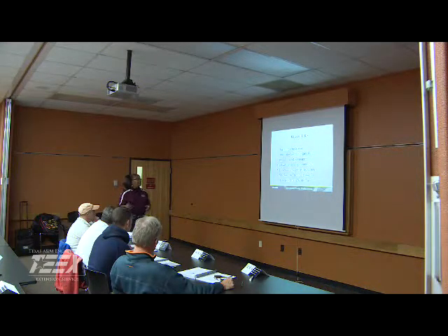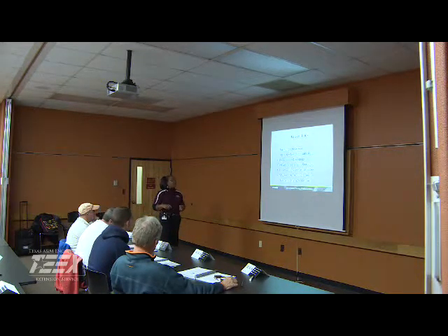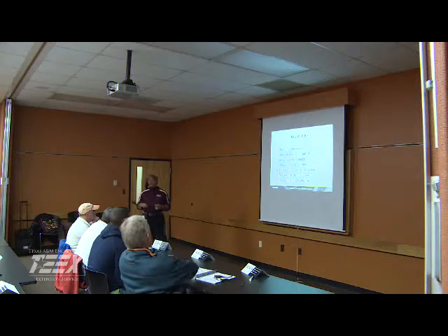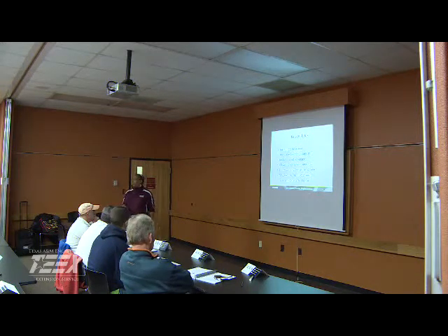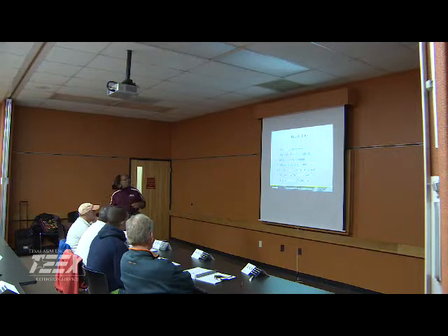So gravel packs will surround the screen. Again, the main purpose is to keep sand out. It allows larger screen openings when you have this gravel pack in place. It lowers the water velocity in the screen, minimizing the incrustation probability.